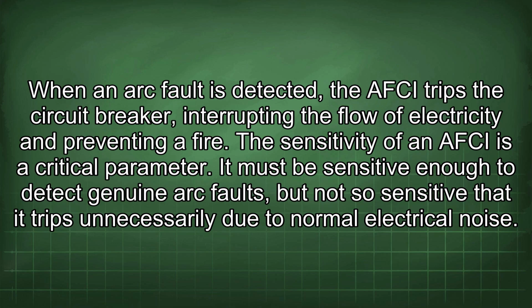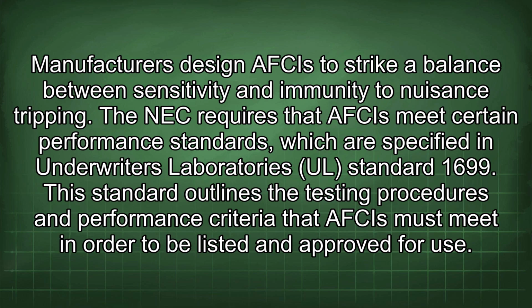It must be sensitive enough to detect genuine arc faults, but not so sensitive that it trips unnecessarily due to normal electrical noise. Manufacturers design AFCIs to strike a balance between sensitivity and immunity to nuisance tripping. The NEC requires that AFCIs meet certain performance standards, which are specified in Underwriters Laboratories UL Standard 1699. This standard outlines the testing procedures and performance criteria that AFCIs must meet in order to be listed and approved for use.